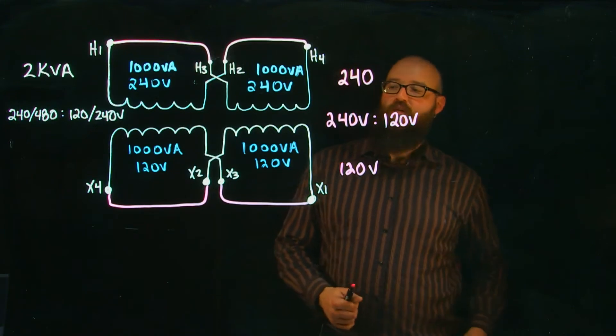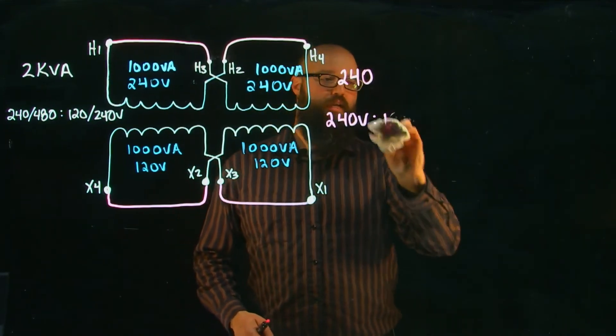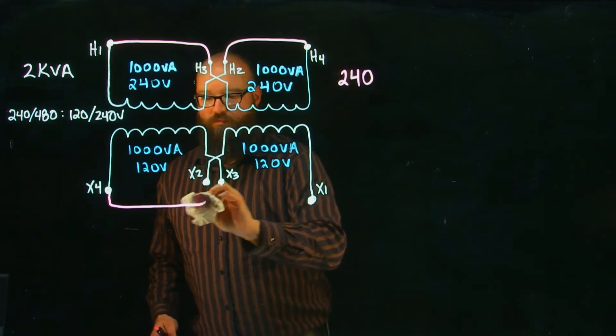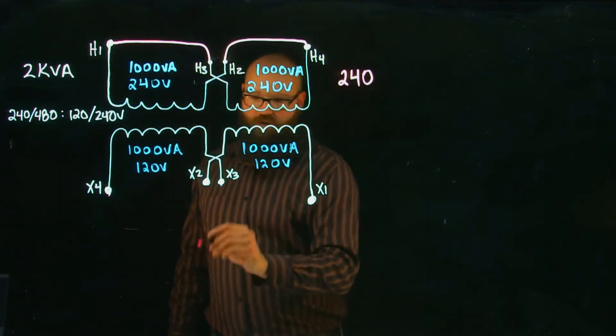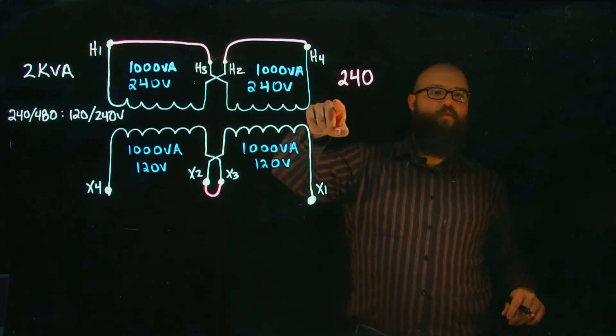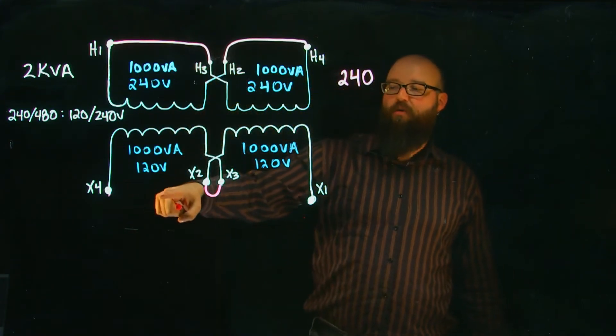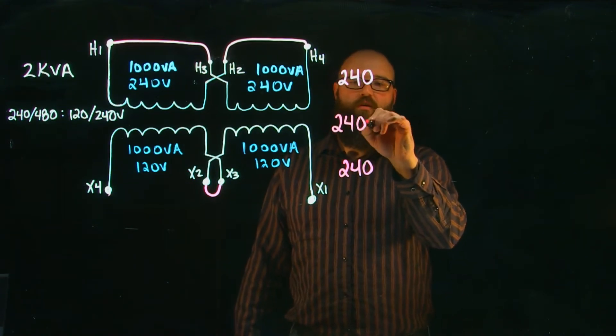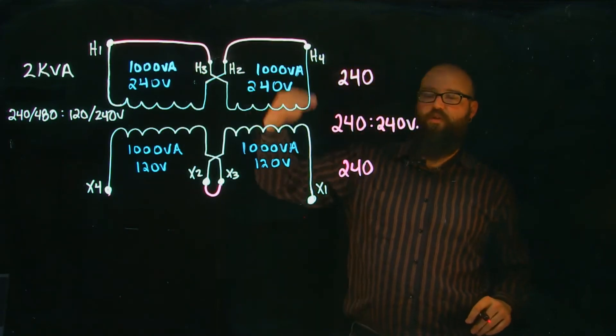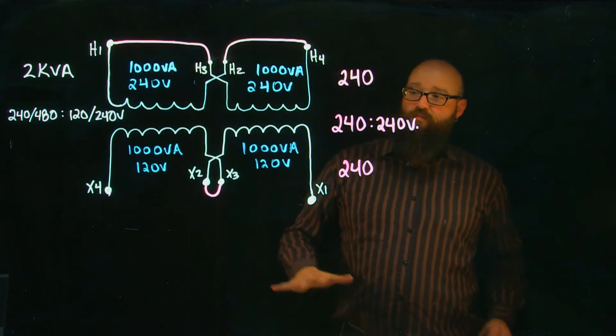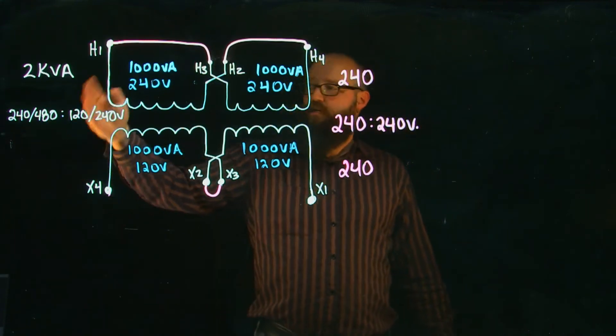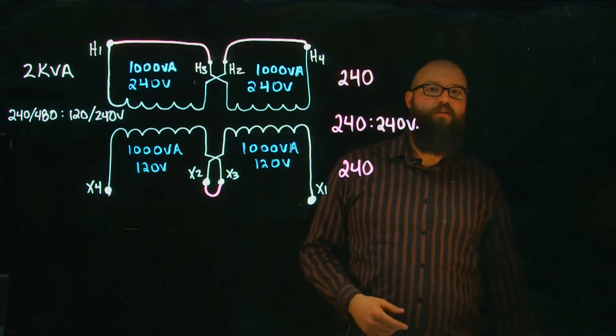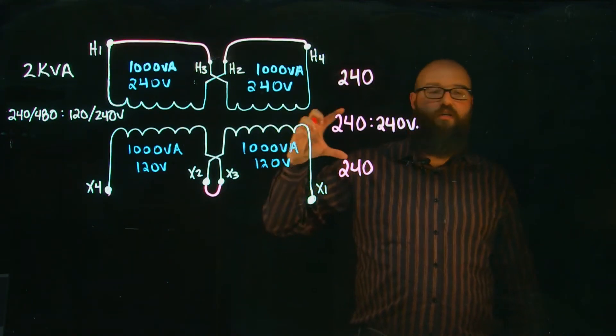The last connection is what happens if we leave the secondary connected in series. With a parallel connection on the primary I still have 240 volts, and with a series connection on the secondary I have 120 plus 120, giving 240 volts out — an isolation transformer with the same voltage in as out. So with a rating of 240/480 step-down to 120/240, each coil is rated for the lower voltage but the higher voltage is achievable with a series connection.